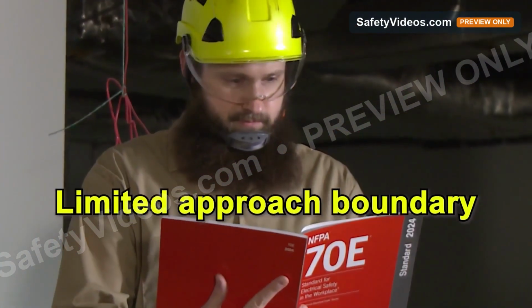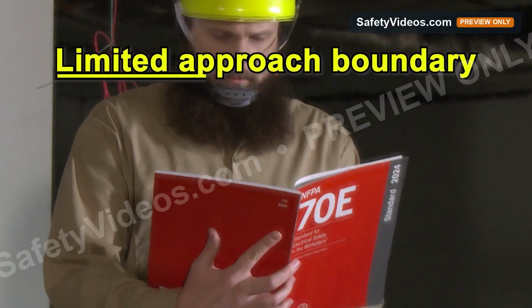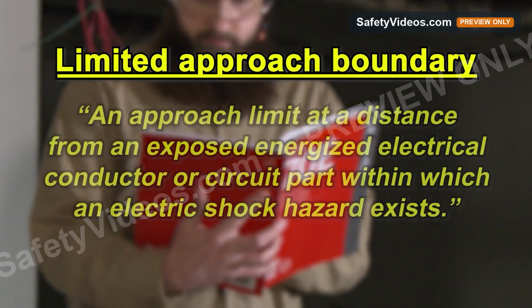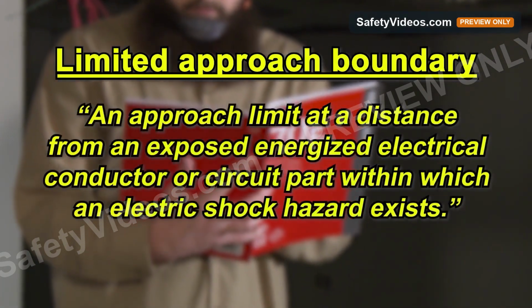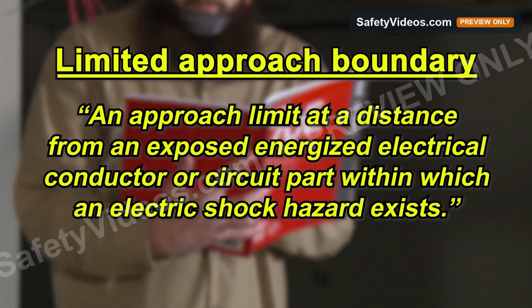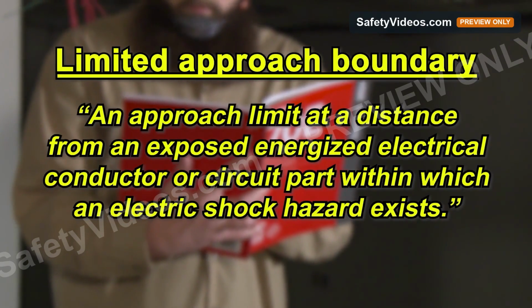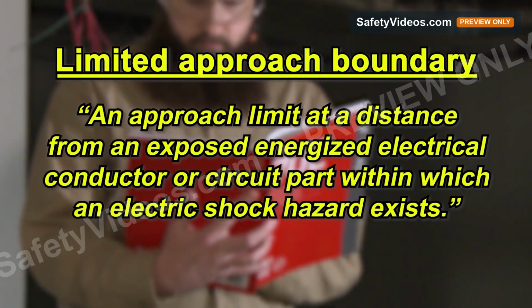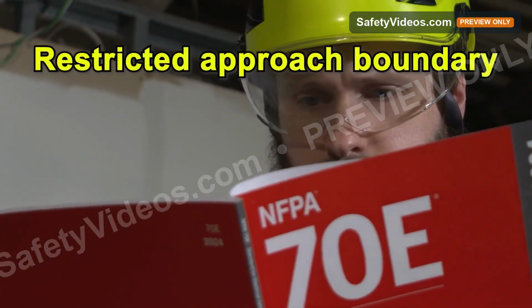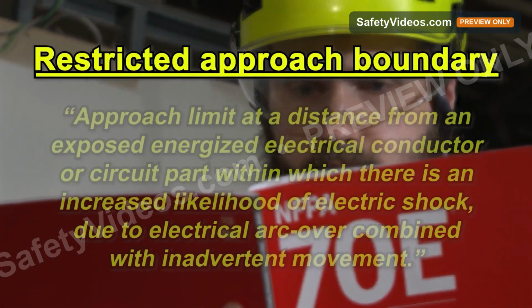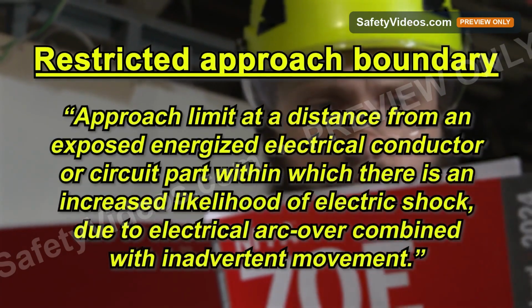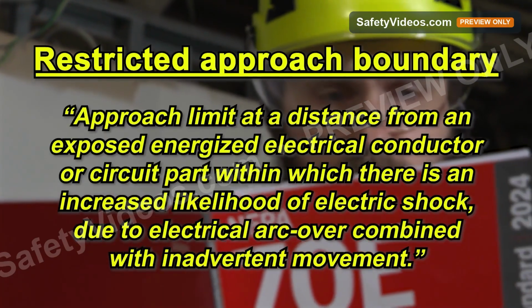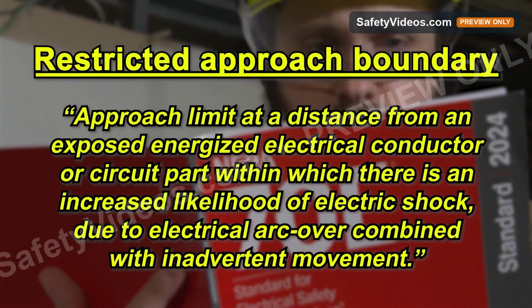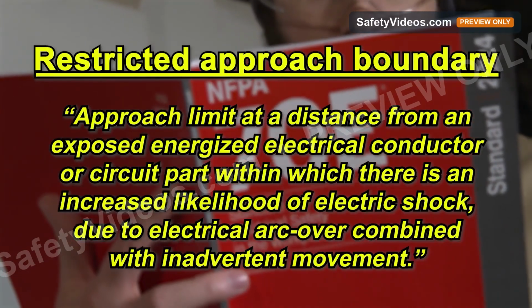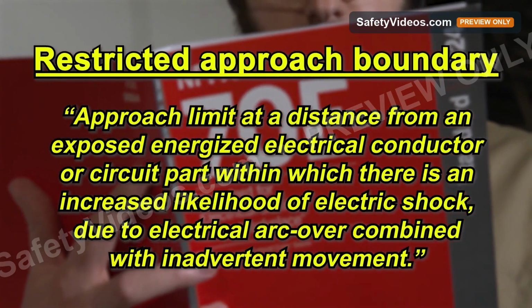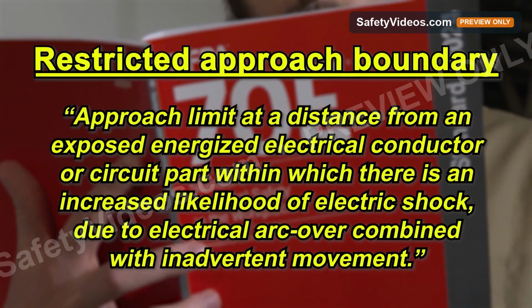The NFPA 70E defines the limited approach boundary as an approach limit at a distance from an exposed energized electrical conductor or circuit part within which an electric shock hazard exists. And the restricted approach boundary is the approach limit at a distance from an exposed energized electrical conductor or circuit part within which there is an increased likelihood of electric shock due to electrical arc-over combined with inadvertent movement.